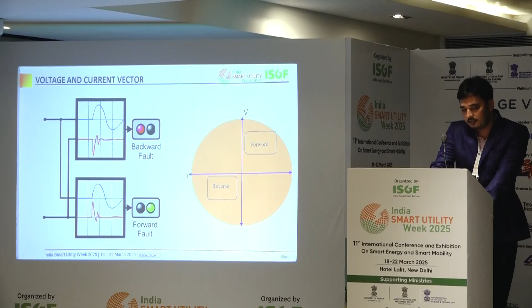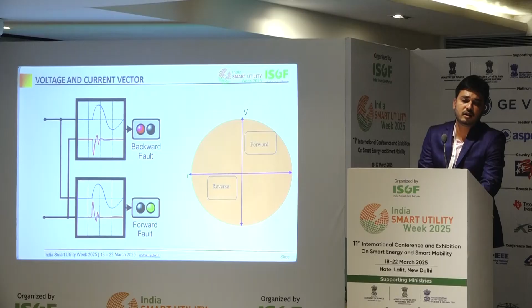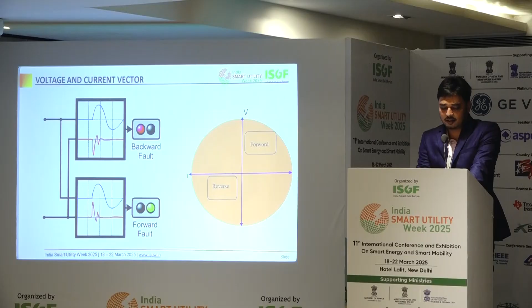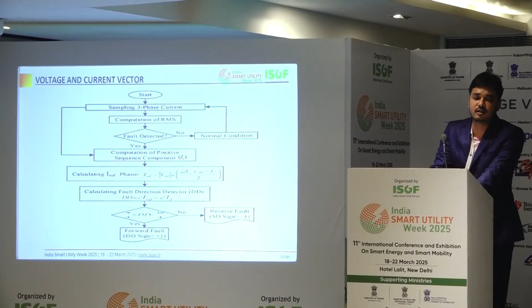The major thing is that the radial or non-directional FPI does not indicate the reversal fault. For the reversal fault, we have to take two cases. One is the voltage and currents. In the forward case, the voltage and currents are in the positive direction, and in the second case the current is in the negative direction. For indicating the negative direction of the current, I have taken an algorithm. I have taken the positive phase sequence as the reference for measurement. When the fault is on the negative side, meaning the reverse direction, the reference current lags or leads between pi by 4 and 3 pi by 4.